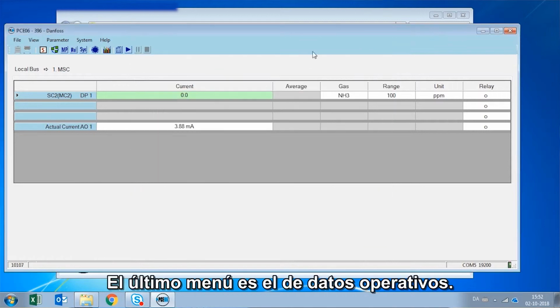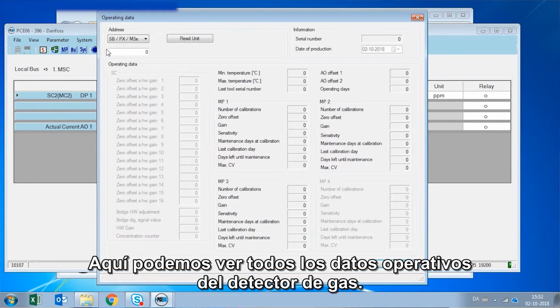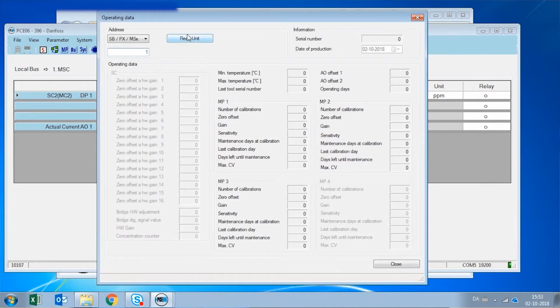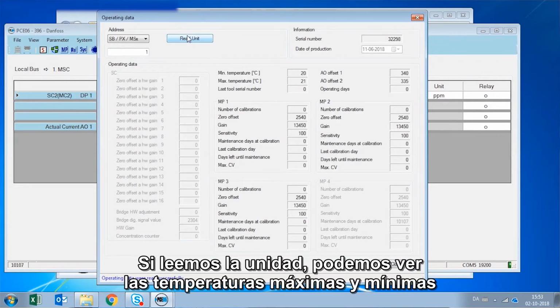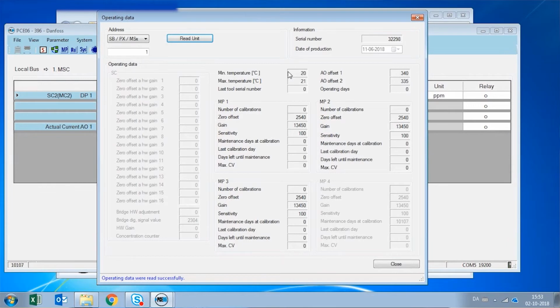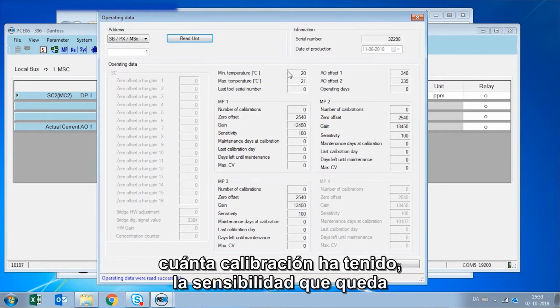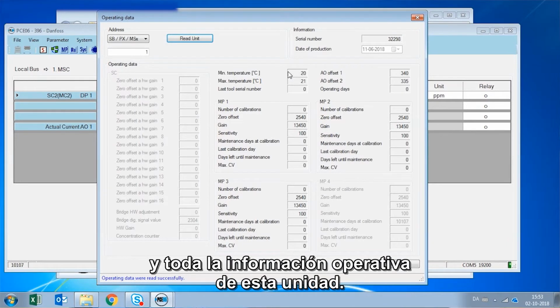The last menu is the operating data, and here we can see all the operating data of our digital gas detector. When we read the unit, we can see the maximum, minimum temperatures that it has seen, how many calibrations it has had, the sensitivity left, and all the operational information on this unit.